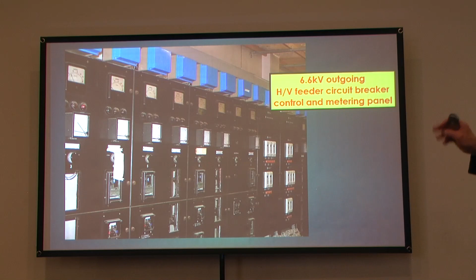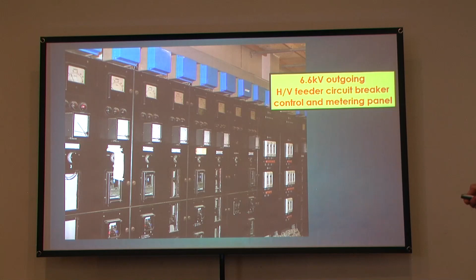This was taken at a weekend on one of the inspection days they had down there, and there's very little load. You can see these are peak reading ammeters, very little load on these circuits, although I suspect that one's out of service, and maybe that one. You can see they've got temporary stick on labels put there. Maybe they're doing maintenance work on part of it. This one actually snuck up a bit overnight, I'd say, with power, whatever that was feeding.